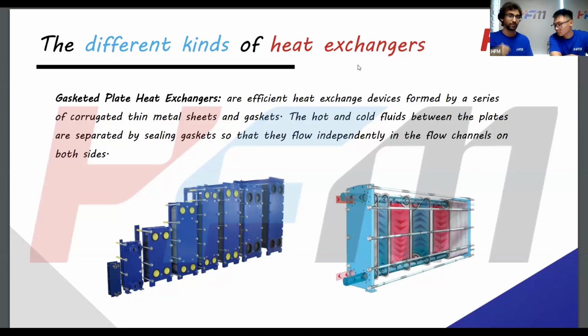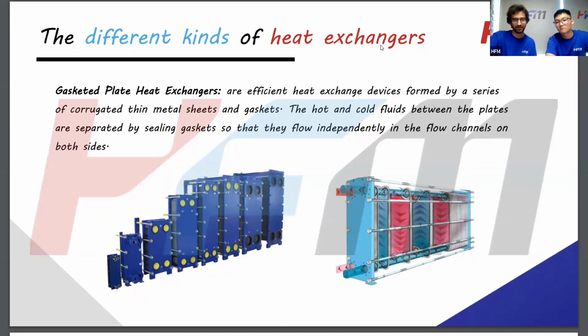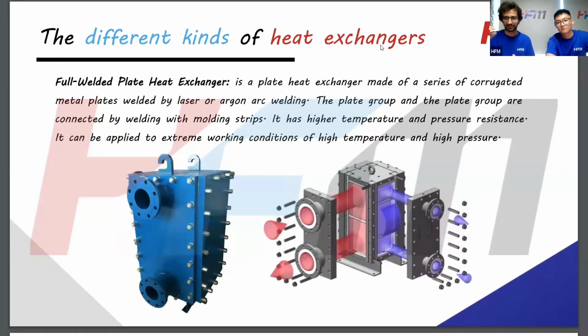But there are other kinds of plate heat exchangers, for example the full weld plate heat exchanger. Instead of having a gasket isolating the fluids, these plates are welded either by laser or argon arc. This is done because many fluids aren't suitable for gaskets, and sometimes the temperature or pressure is too high for gaskets to support, so it makes more sense to use the full welded plate heat exchanger.